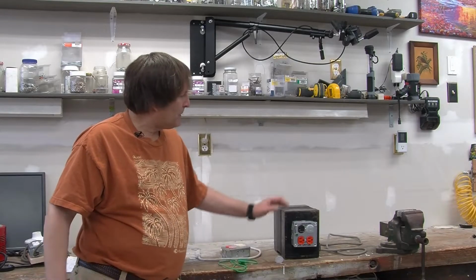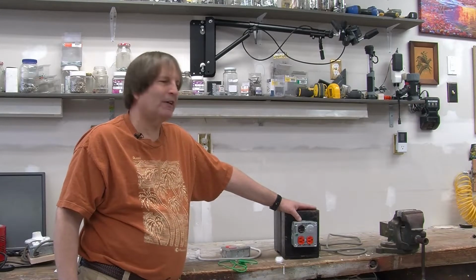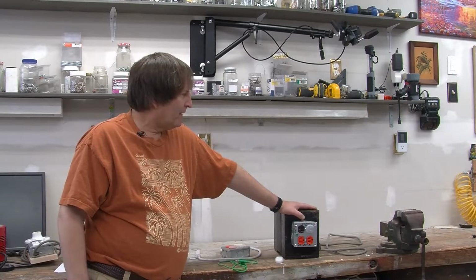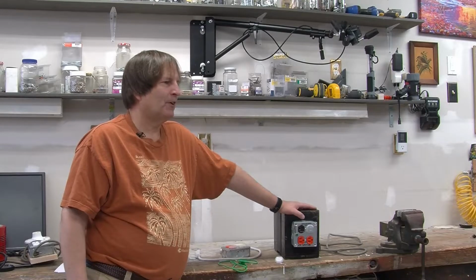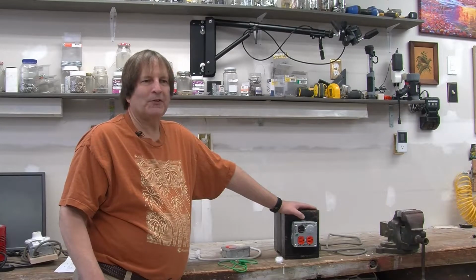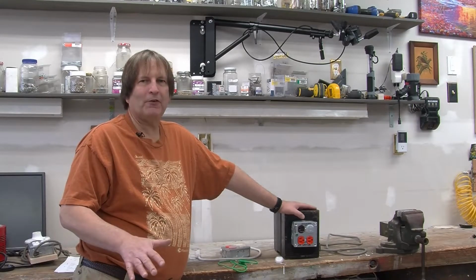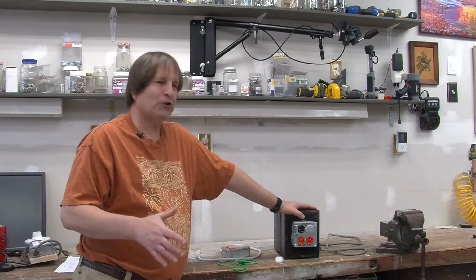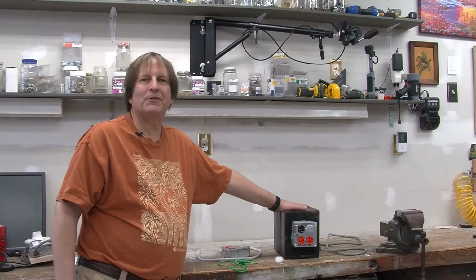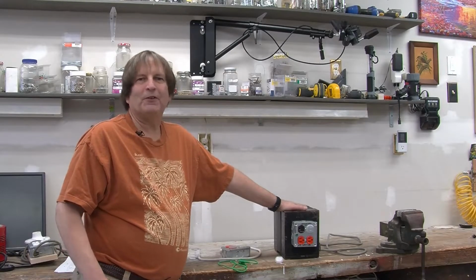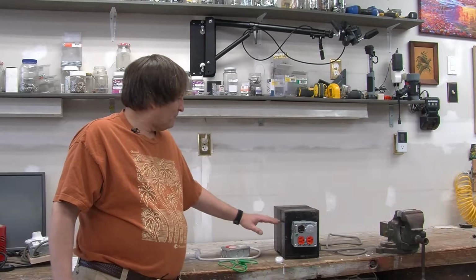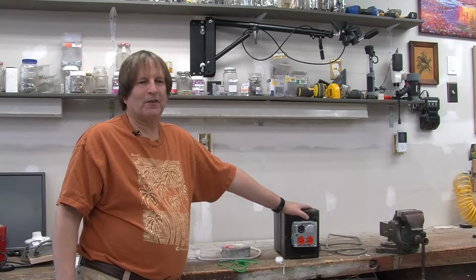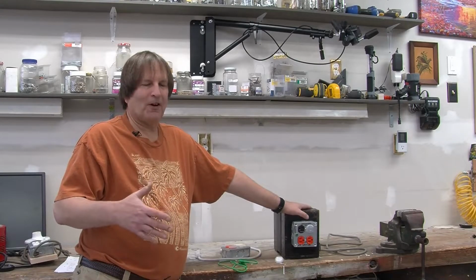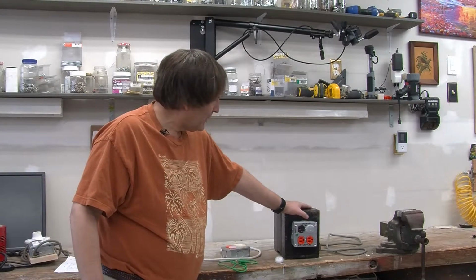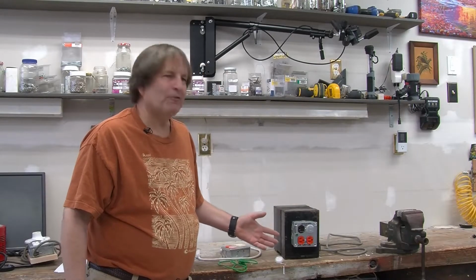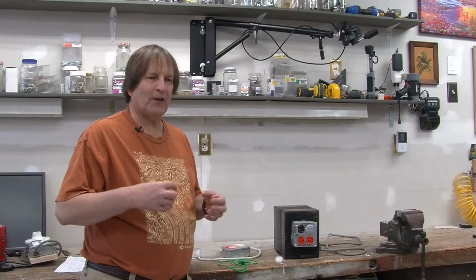Same sort of thing but slightly different might happen with the isolation transformer. And in particular, if you have a device that might have a fault between some component in the device and its chassis, which is then grounded, well, now you have a connection to ground that bypasses the isolation transformer. And so you can get an electrical shock because the isolation transformer is no longer providing a complete disconnect from earth ground.